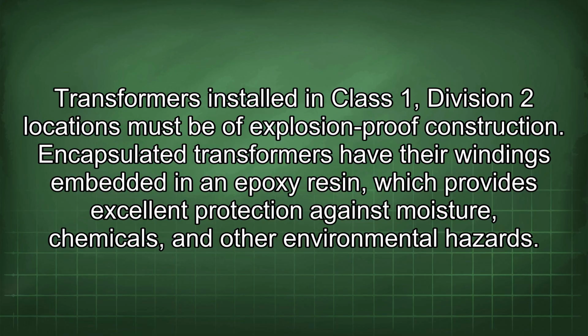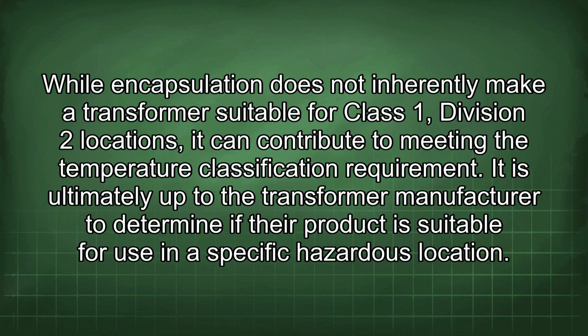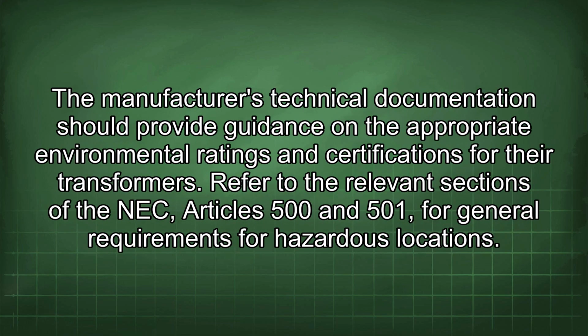Encapsulated transformers have their windings embedded in an epoxy resin, which provides excellent protection against moisture, chemicals, and other environmental hazards. While encapsulation does not inherently make a transformer suitable for Class 1 Division 2 locations, it can contribute to meeting the temperature classification requirement. It is ultimately up to the transformer manufacturer to determine if their product is suitable for use in a specific hazardous location. The manufacturer's technical documentation should provide guidance on the appropriate environmental ratings and certifications for their transformers.